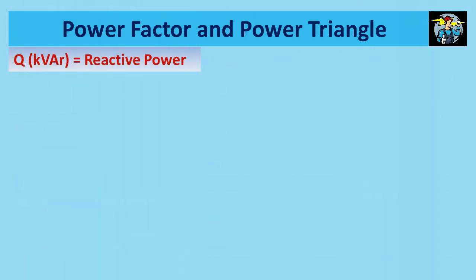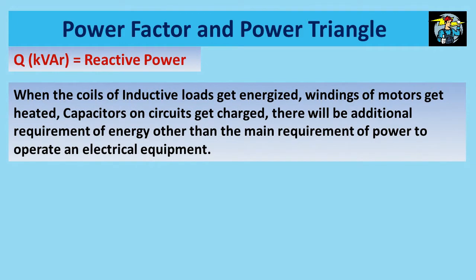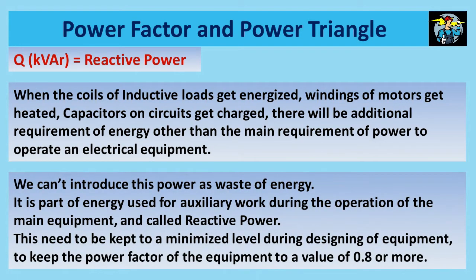Then what is reactive power? When the coils of inductive loads get energized, windings of motors get heated, capacitors on circuits get charged, there will be additional requirement of energy other than the main requirement of power to operate electrical equipment. We can't introduce this power as waste of energy. It is part of energy used for auxiliary work during the operation of the main equipment, and called reactive power. Reactive power need to be kept to a minimum level during designing of electrical equipment to make sure the power factor is within the range of reasonable acceptable value between 0.8 and 1.